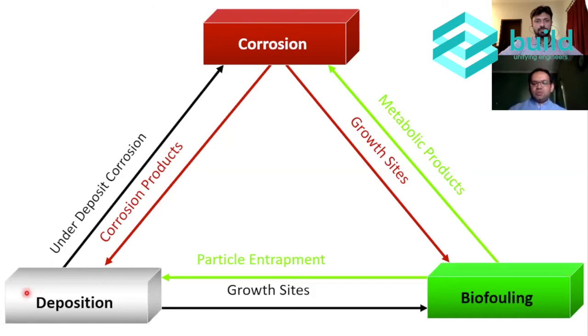The other problem is deposition, caused by salts present in water. They can settle down when solubility limits are exceeded, and there's also the possibility of suspended particles depositing on the heat exchanger plates. The third problem is biofouling.